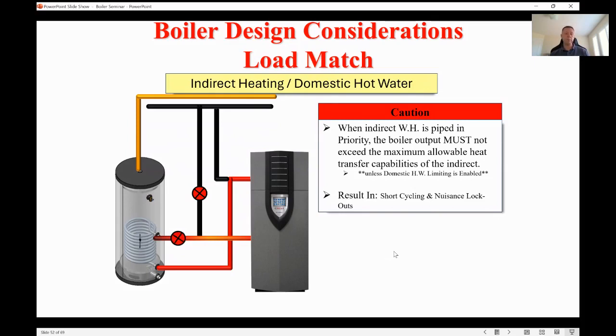Well, what's happening? The coil's only taking 500,000 out. So it'll overshoot, it'll go 180, 185, whatever you have it, and then it'll just shut itself down on temperature. Well, the tank's still cold. It'll wait till that cools off a bit, strip that heat out, and say, turn on again. It'll turn on, off, on, off. And once you get into that cycling situation, which you want to avoid.